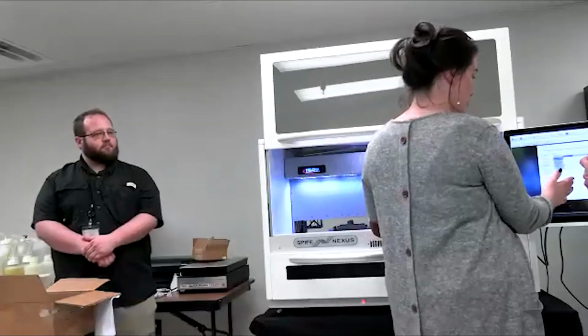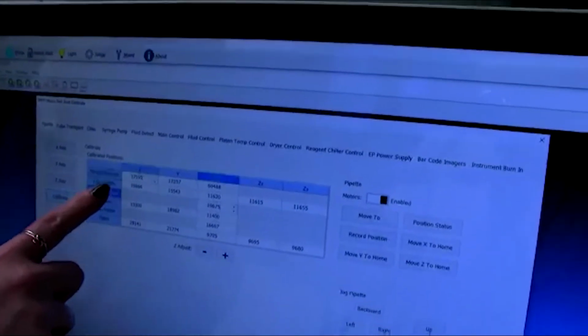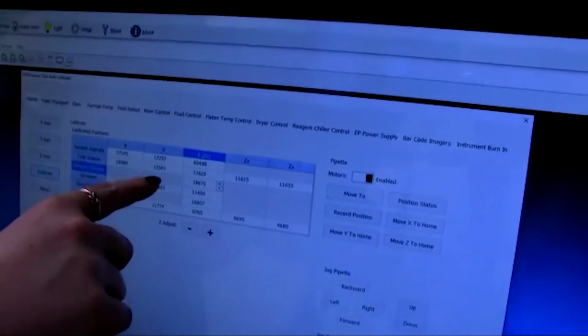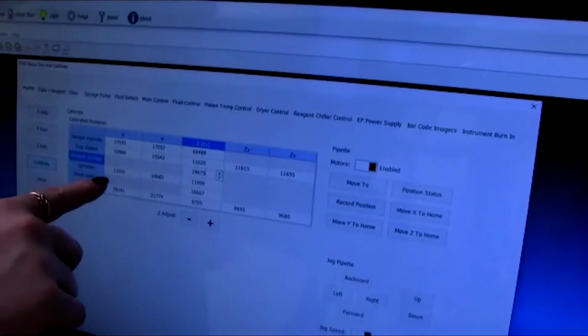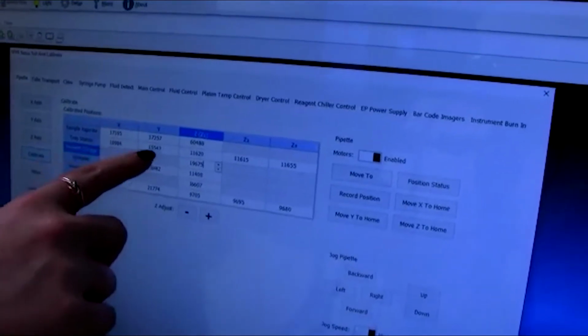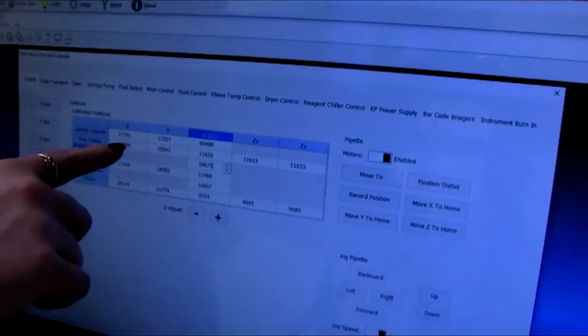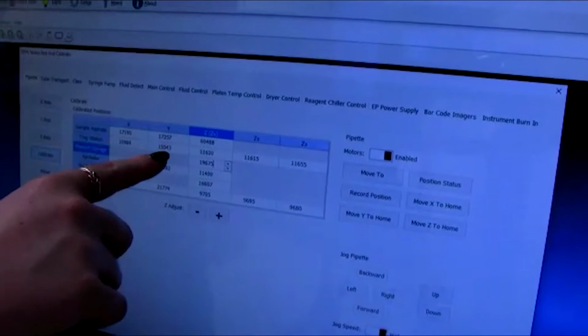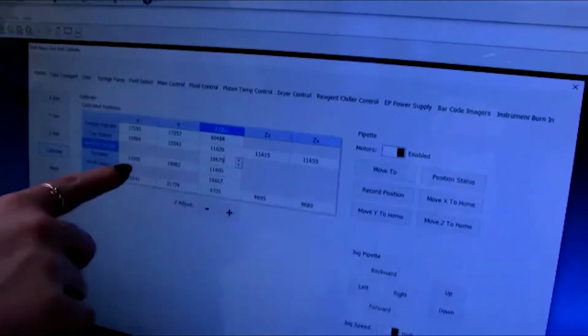All right, so that would be a pipette position. So I would go to calibrate. All right, so now we're on the pipette calibration screen. That particular position is called reagent storage. You'll notice there's no X and no Y for this position. Similarly with the wash station, there's no X and no Y to calibrate. That's because the X's and Y's of those positions are calculated by the machine from your tray station value. So this tray station X and tray station Y, the machine automatically calculates these other X's and Y's from your tray station values. So you'll want to go in order.